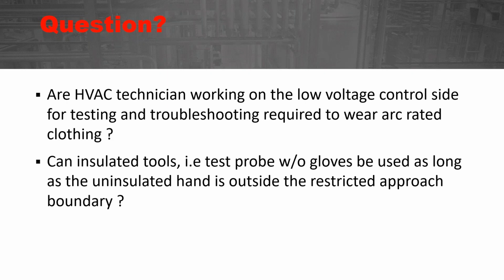Is an HVAC technician working on the low voltage control side for testing and troubleshooting required to wear arc-rated clothing? And to follow up with that, can insulated tools, that is test probes, without gloves be used as long as the uninsulated hand is outside the restricted approach boundary? I think this is for you, Charlie.